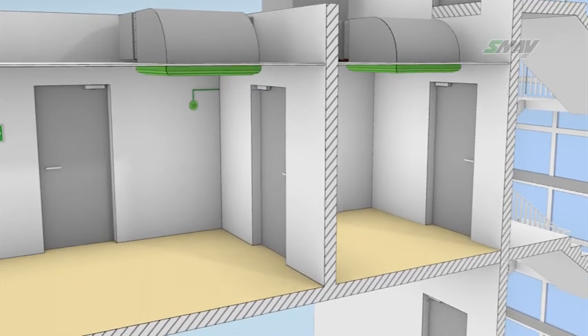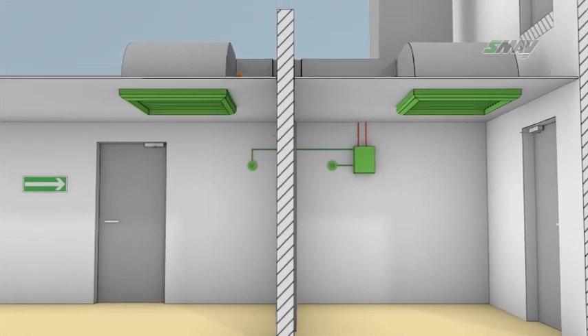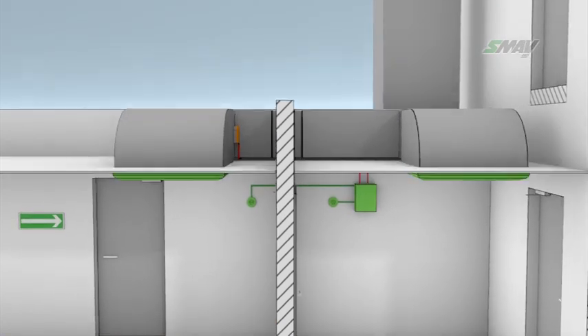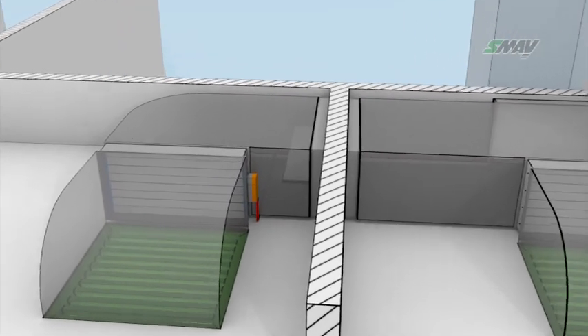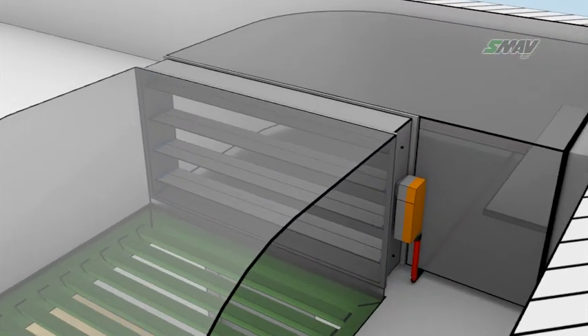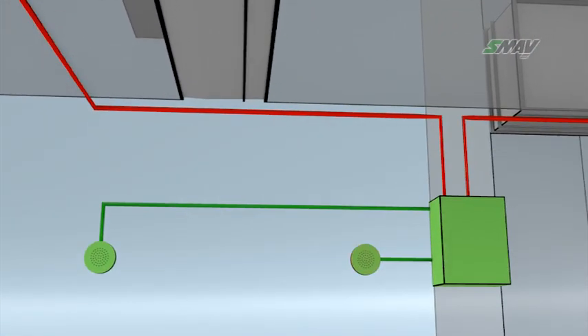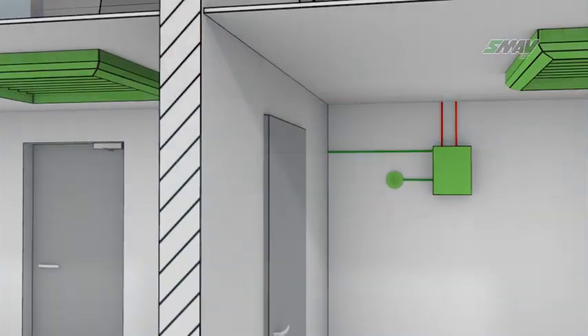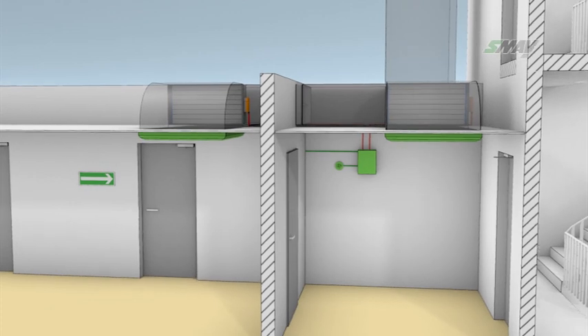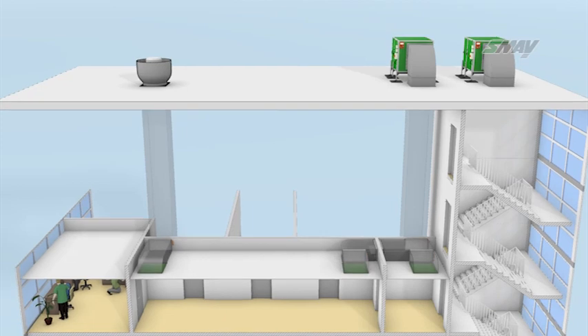An alternative solution to air transfer dampers is the use of an electronically controlled air transfer, which constitutes a duct with two branches, one to the firefighting lobby and the other to the corridor. Each branch is equipped with electronically and mechanically coupled multi-blade dampers. The system also includes a regulator with two pressure measurement points, one in the lobby, the other, the reference, in the corridor. The proposed system is an answer to the smoke extraction air compensation problems for corridors operated by constant capacity smoke extraction fans.